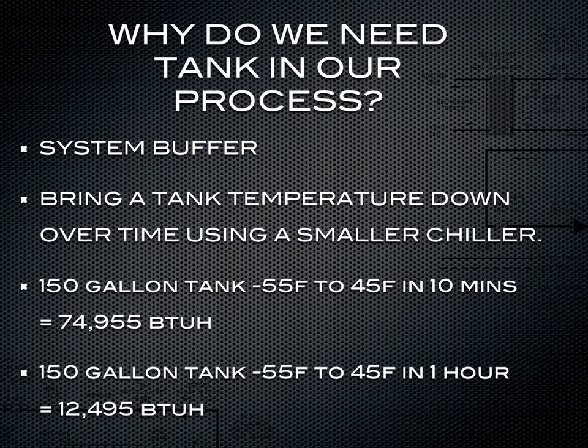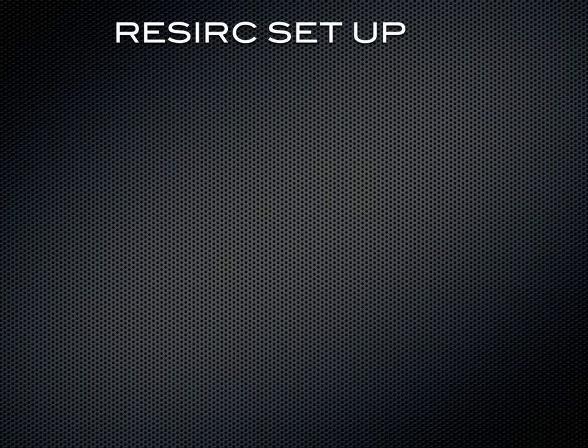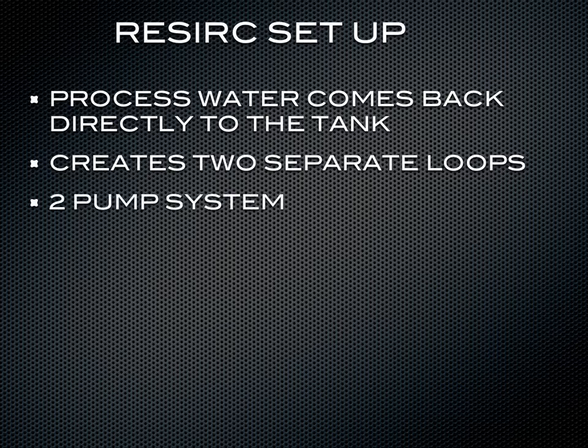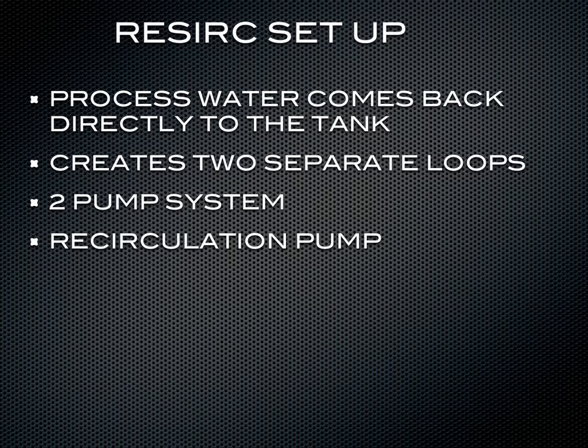This is also a good solution if you have a low demand of flow rate to your process. A recirc tank setup is where the process water comes back directly to the tank. On a once-through chiller, the fluid comes back directly to the chiller evaporator. In the recirc setup, it creates two separate loops using a two-pump system. The first pump is the recirculation pump, whose job is to circulate the fluid to the chiller evaporator and back to the tank, always servicing that evaporator with 2.5 to 3 gallons per minute. The recirc pump also always keeps the tank temperature at your desired leaving water temperature — so if you have 55°F water going out to your process, that tank will be kept at 55°F. The second pump is the system pump, whose job is to pull that cold water off the tank and bring it out to your process to cool your equipment.